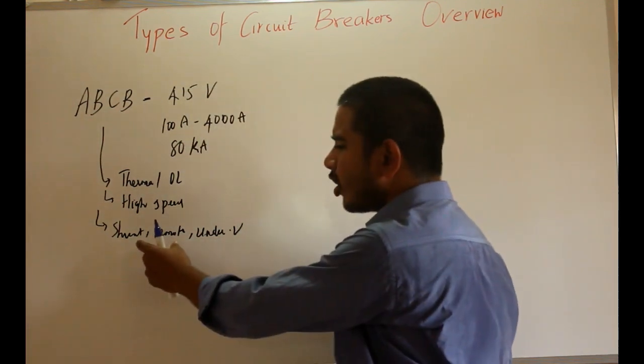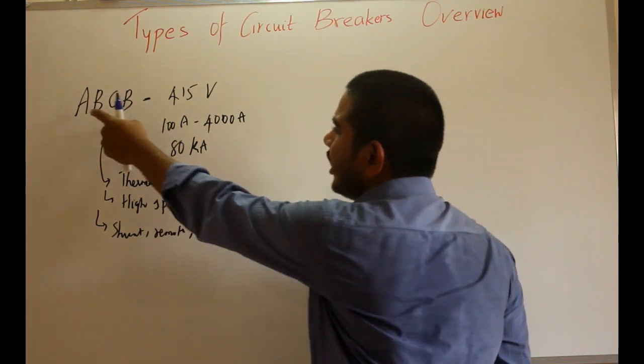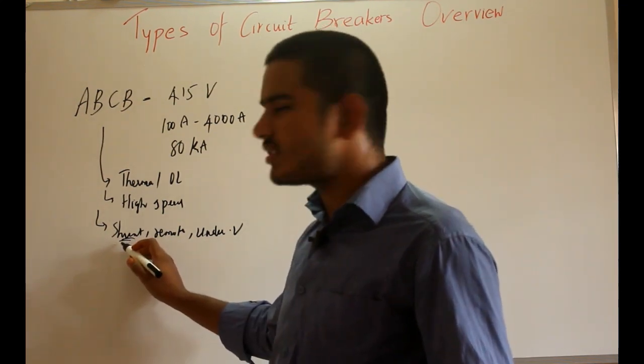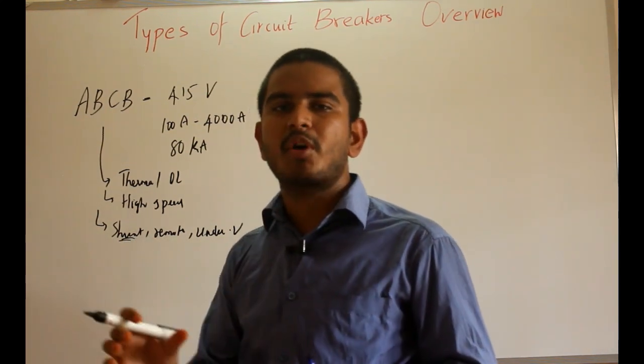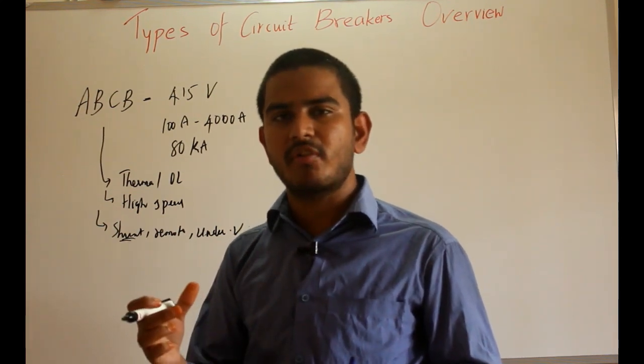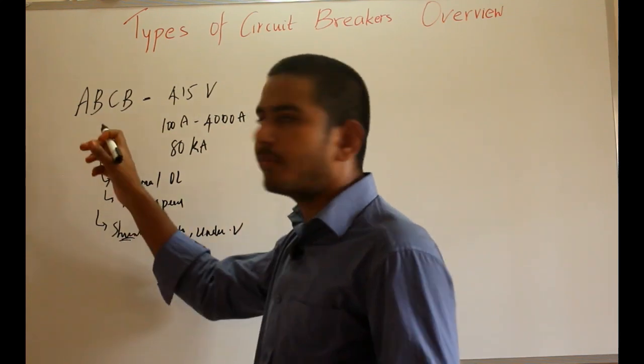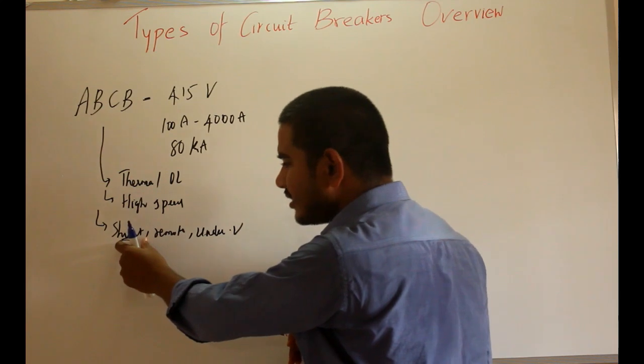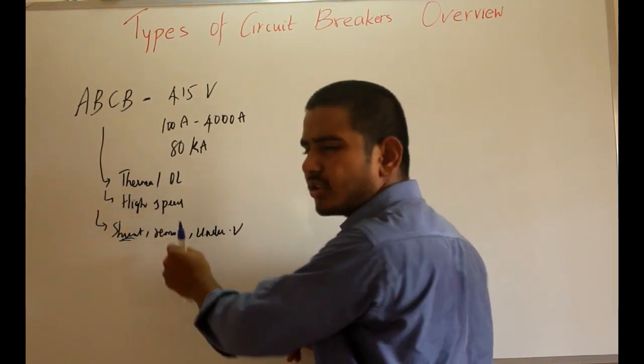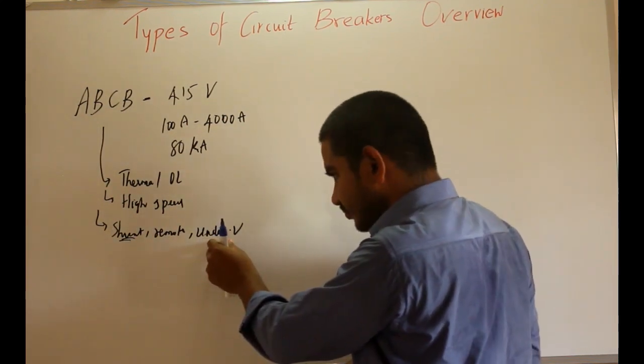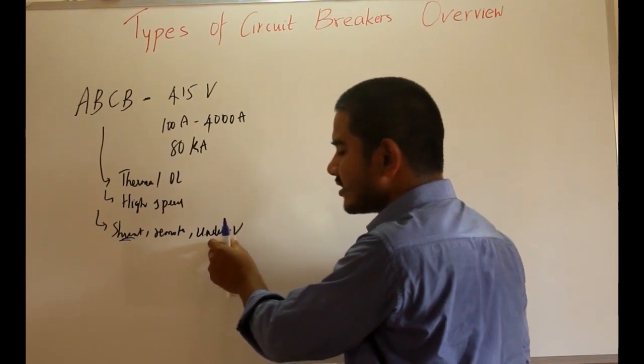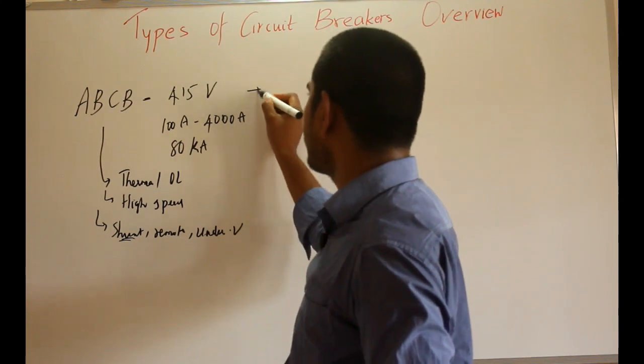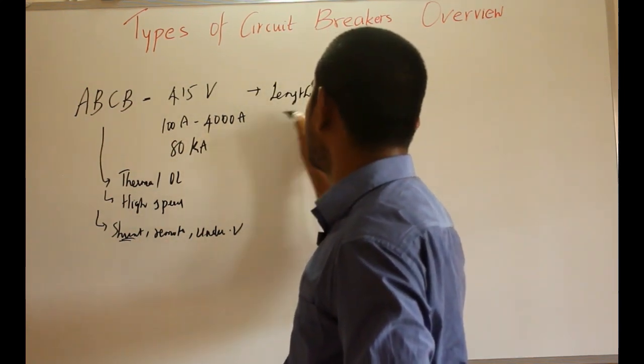Optional accessories present in the air break circuit breaker include shunt trip, remote trip, and under voltage release. The shunt trip is an optional device where you must provide power externally to the shunt trip terminals to trip the breaker — it cannot work with the breaker's own power. Remote trip allows tripping from a remote area, and under voltage release trips when voltage falls below a threshold.